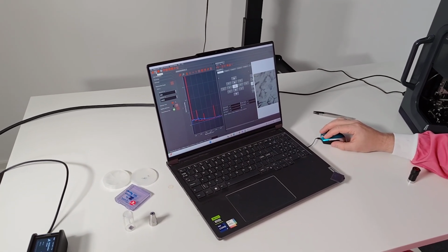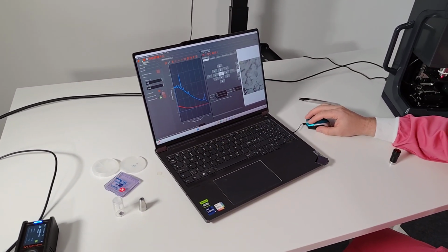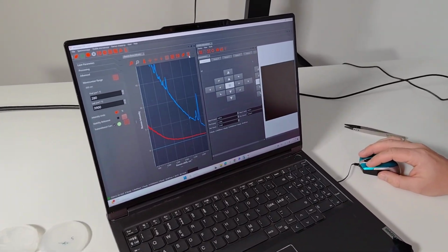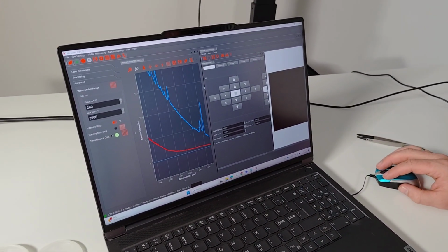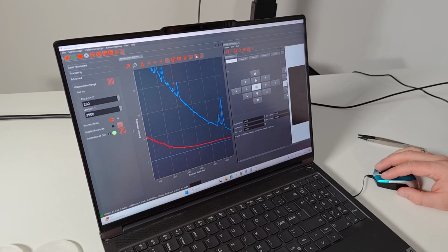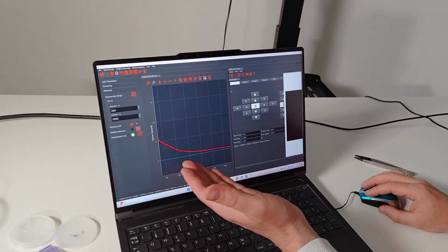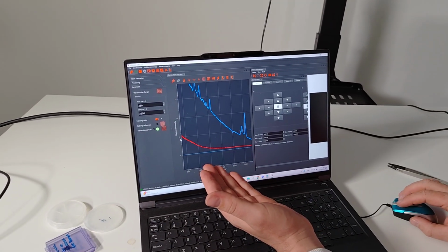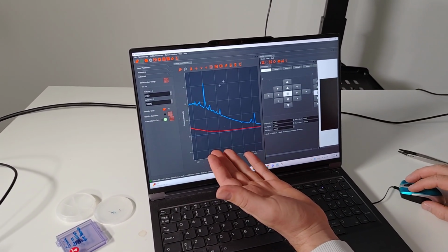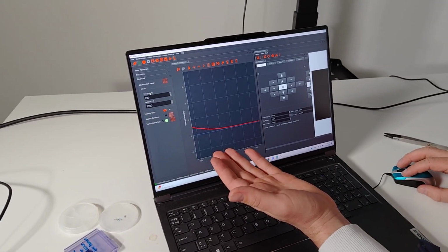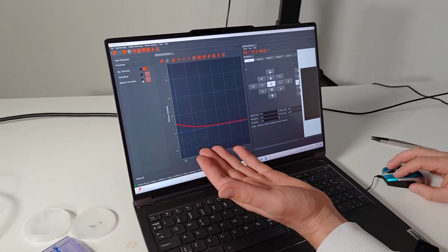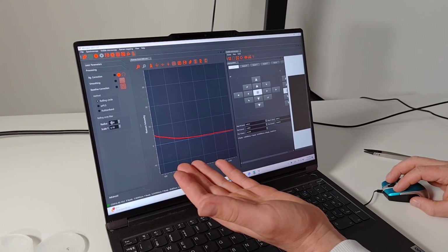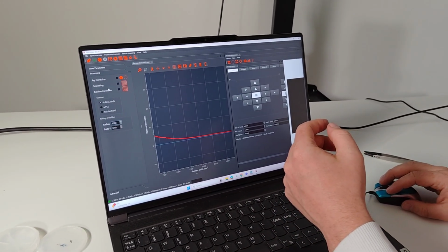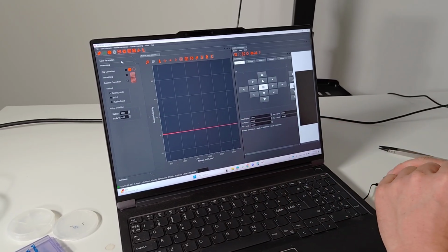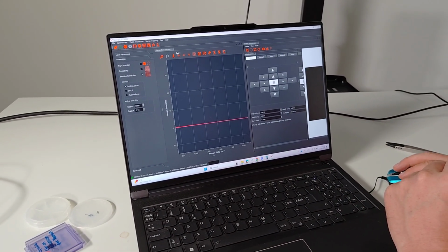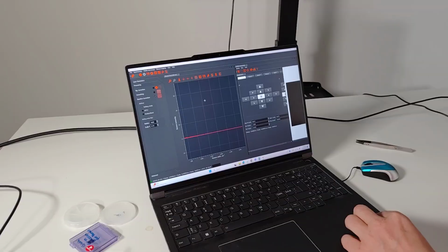And it is connected. So let's say if I turn on the light, I would see a live spectrum with reference and main channels on the software. I would remove the reference of polystyrene. We simply don't need it. And I also would probably include baseline correction based on, let's say, rolling circle, and we click apply. So we see it flat. So there is no extra luminescence and so on visible. Good. Now how about graphene?